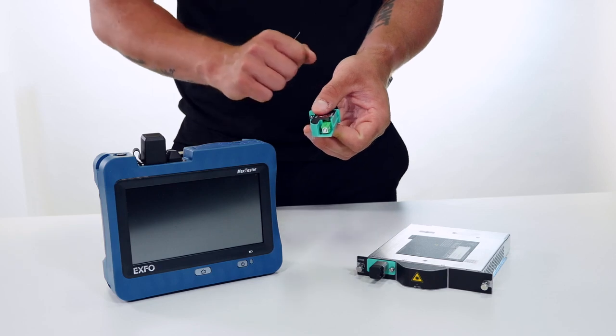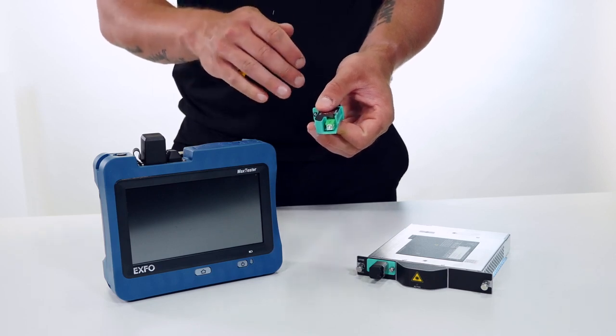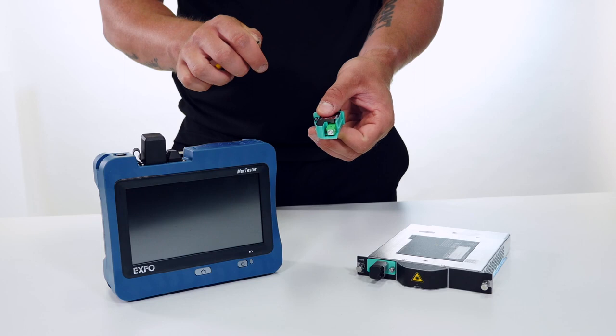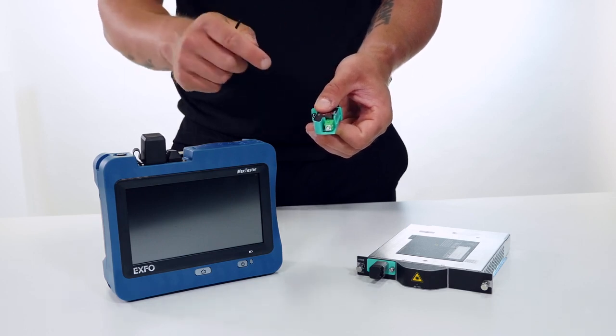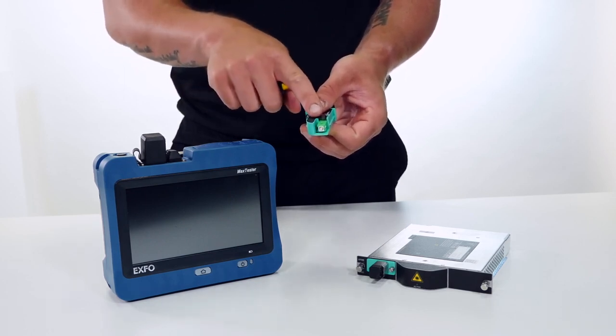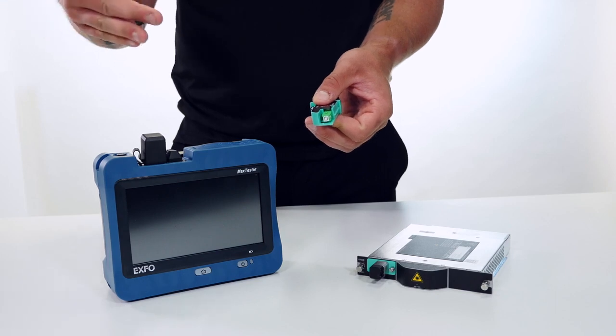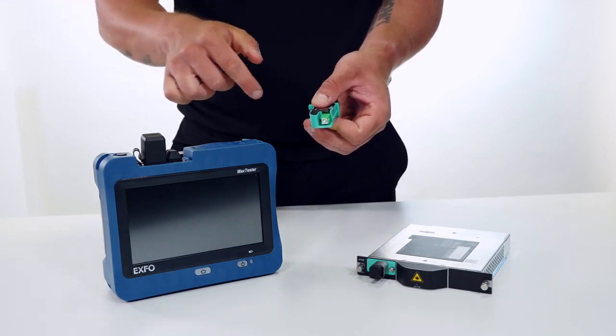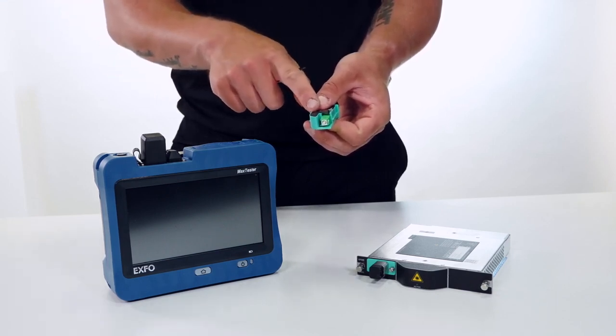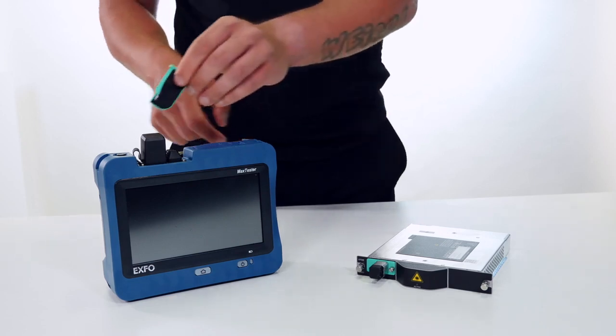If we change the swap out connector, we do not change the calibration date. So it's not reset, it's not nullified. If I have to calibrate my internal connector in 6 months, I still have to calibrate in 6 months, even if I've changed my connector itself.